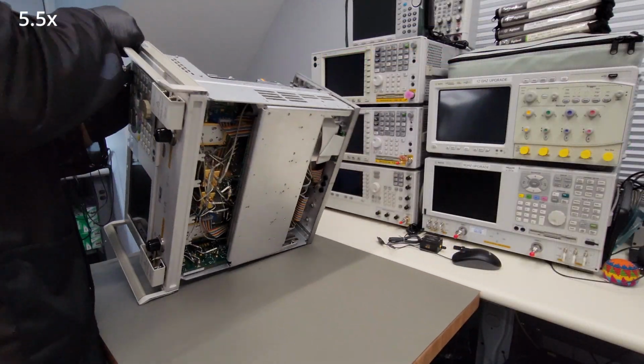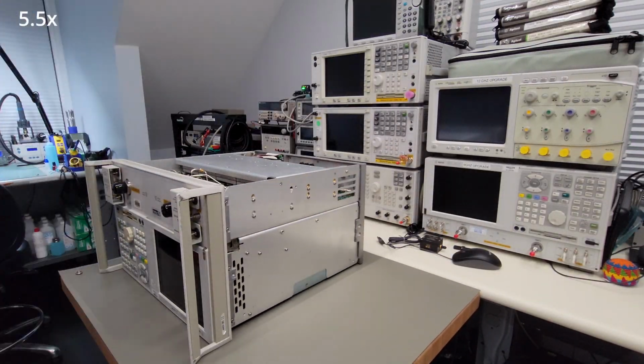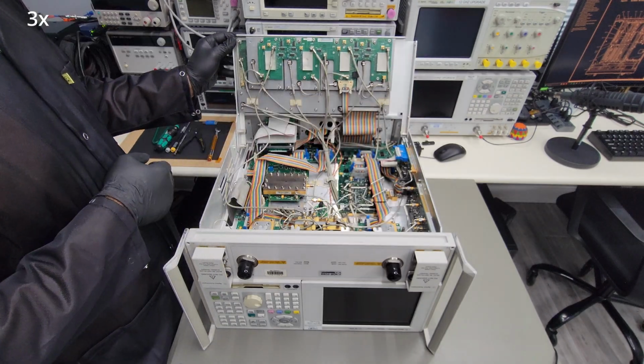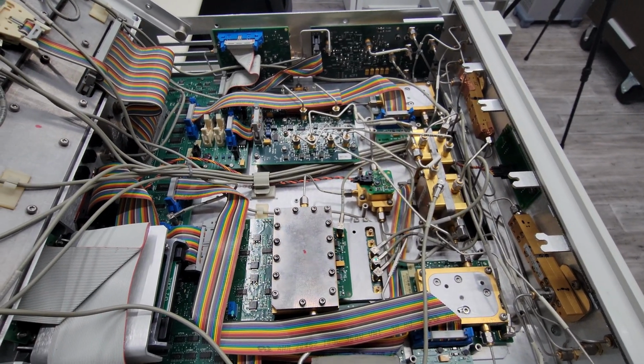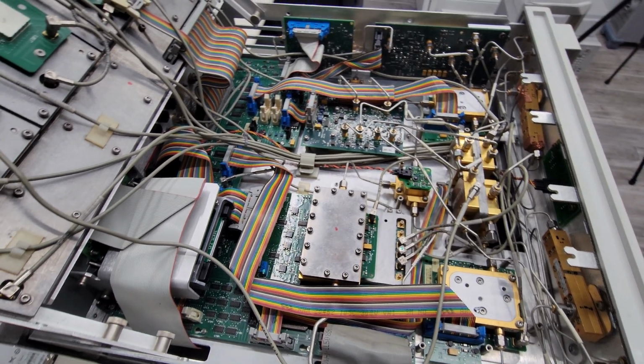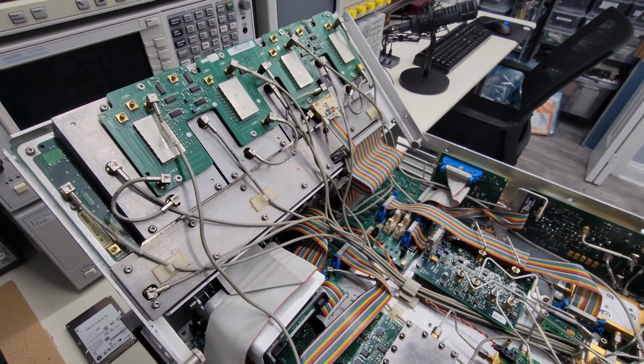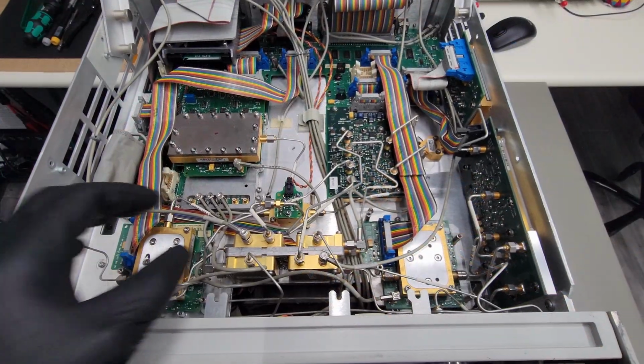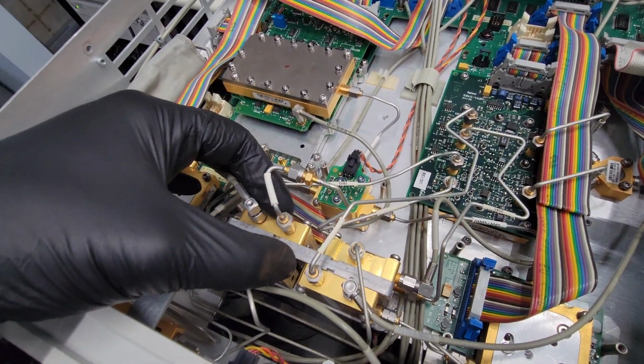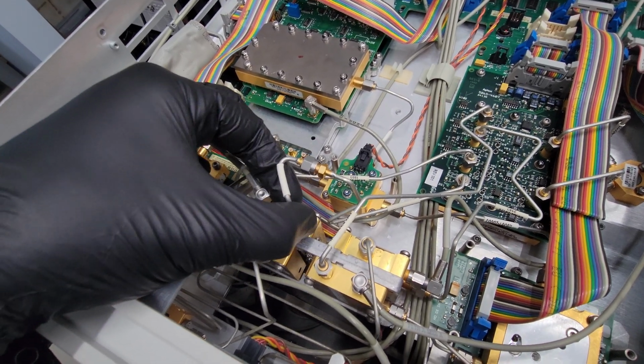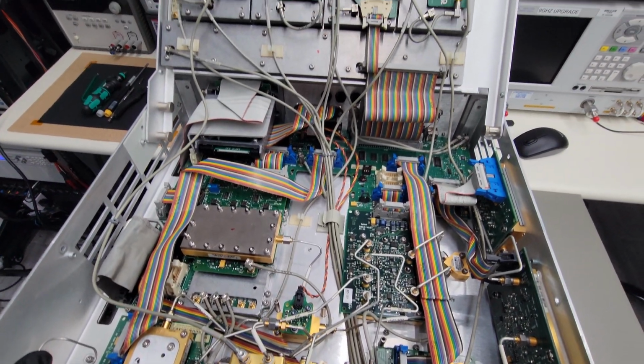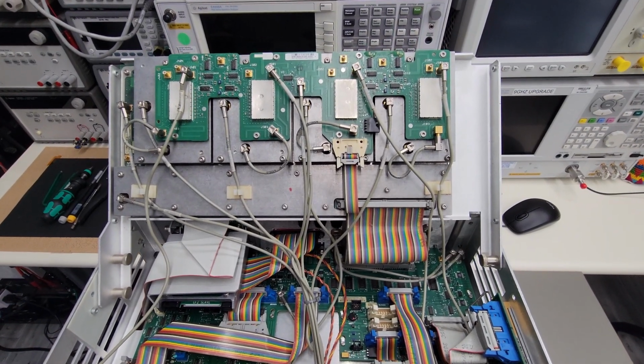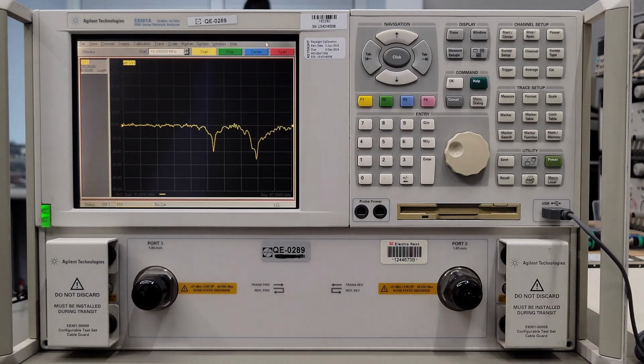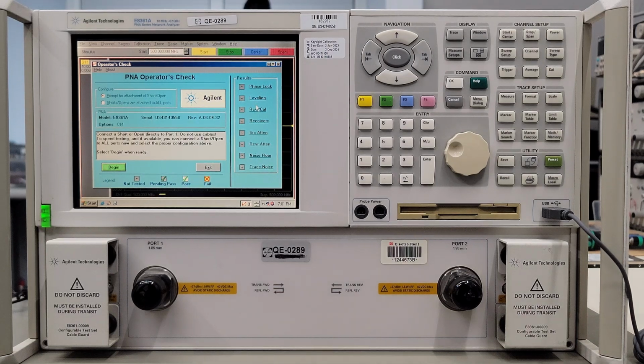To be thorough, I'll flip the unit over and check all of the connectors on the test set as well. Here, we can see the majority of the RF components that make up the analyzer. While poking around, I did notice a loose RF connector on one of the high band receiver mixers. I'll go ahead and clean any digital connectors I can access and make sure that all of the RF connectors are torqued properly. After completing the final checks on the test set, we do a cold power up the next day to find the usual EEPROM error is no longer present. Additionally, no unlocks have manifested after letting the unit warm up for several hours.